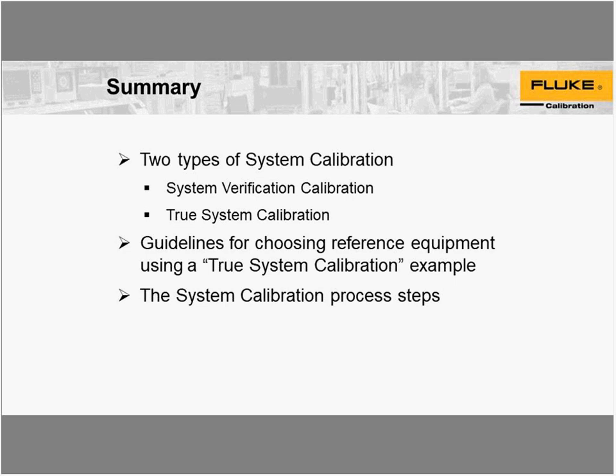Sixth question. Can you use as-found resistance measurements for as-left and generate new coefficients for mapping the temperatures? There are two separate things. When you're using the as-found resistance, you're using the as-found reference temperature and the as-found DUT, UUT resistance to generate coefficients. You can't use the same resistance measurements for your as-left, and you can't use your as-left resistance measurements to generate coefficients for as-found temperatures. You have to keep those separate. That's what the calibration is: you're taking your as-found data, calculating the coefficients, and then taking as-left.